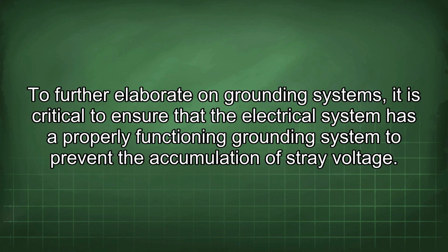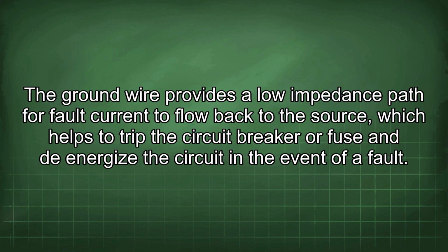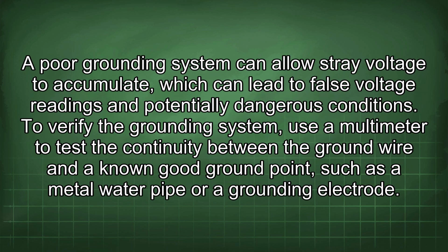To further elaborate on grounding systems, it is critical to ensure that the electrical system has a properly functioning grounding system to prevent the accumulation of stray voltage. The ground wire provides a low impedance path for fault current to flow back to the source, which helps to trip the circuit breaker or fuse and to de-energize the circuit in the event of a fault. A poor grounding system can allow stray voltage to accumulate, which can lead to false voltage readings and potentially dangerous conditions.